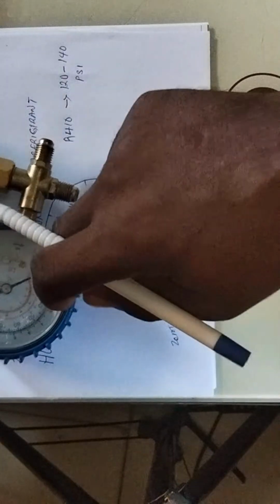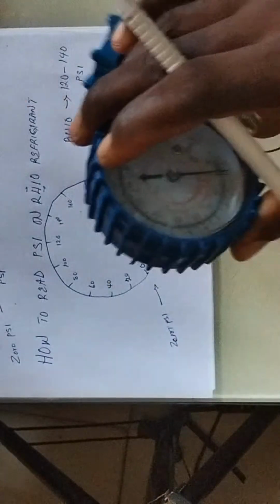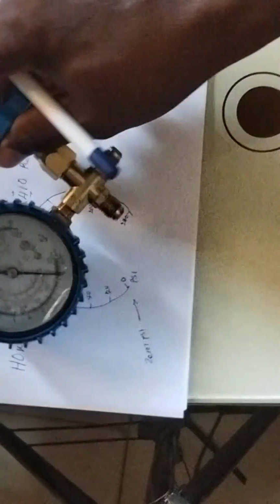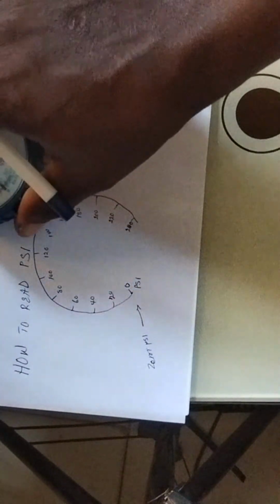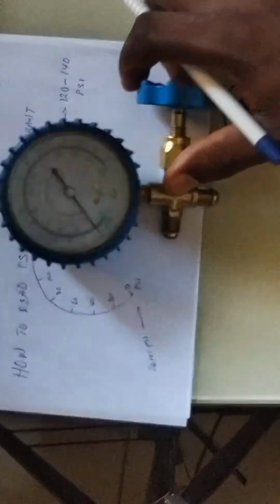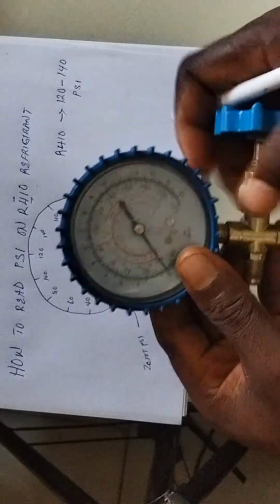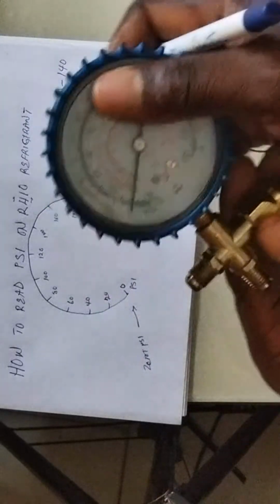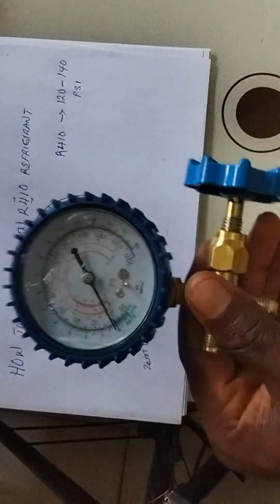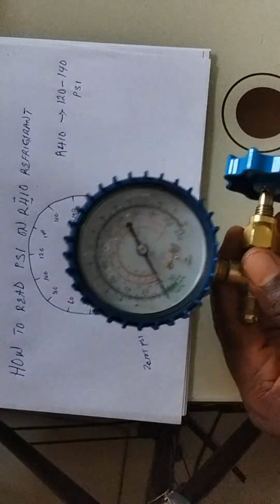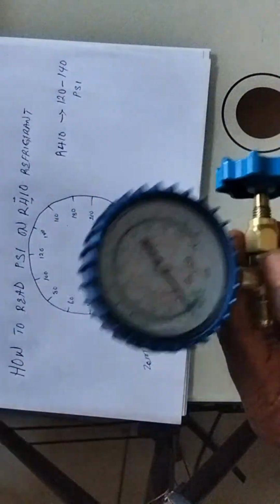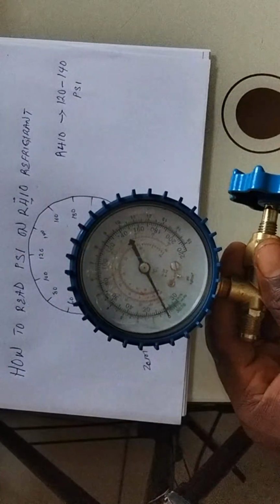That is one of the functions of using a gauge while working. If you have refrigerant on the system already, the gauge will tell you how much refrigerant you have on it already, how much refrigerant you need to add to the system, and how much refrigerant needs to saturate that air condition. Understand? That is why you need a gauge while working. I always advise most technicians that when they are working with a system like an air condition or a refrigerator, they should try their very best to use a gauge while working, because it helps them to know the status of a particular system, why a system is not cooling, why it's not working, or why it's not efficient. Understand? This helps them to understand that.